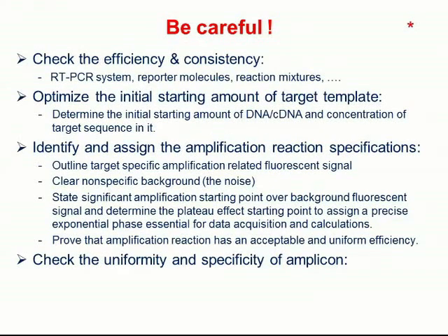Non-specific background clearance, the noise removal, is another procedure that has to be done by the system or by the users. So there are some rules to be defined to remove this background, and also to tell the system that the specific amplification starts over that point, which means the threshold level. So all these parameters have to be checked before starting the system.